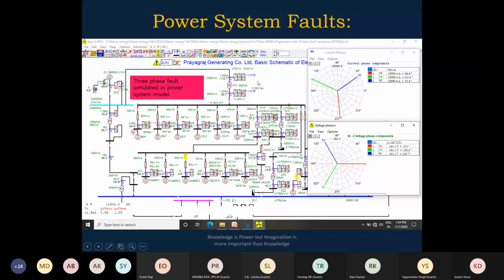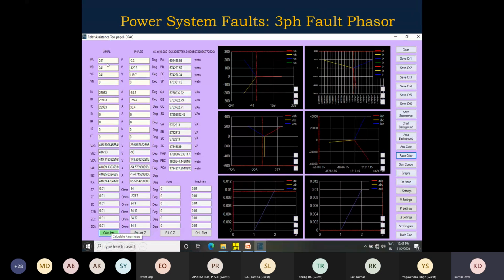And you see here, the fault current is 23.993 kiloampere. The CT ratio is 700 by 1. So fault current is 23.993 kiloampere in all three phases. And the fault voltage is 241 volt. Now you look at it here, when the fault voltage is 241 and fault current is 23.993, you see the phasor diagram, and you look at it here, the impedance is 0.01, 0.01, 0.01 in all three phases. ZA, ZB, ZC, ZAB, BC, CA.